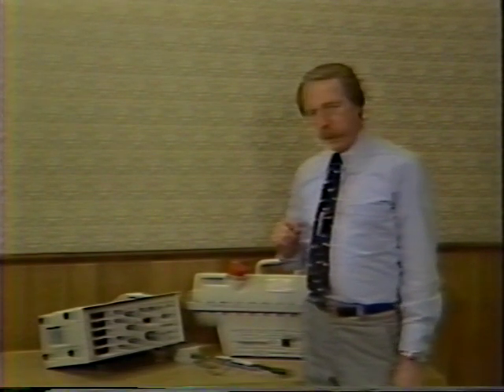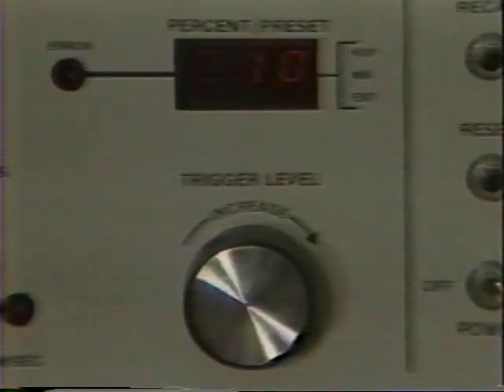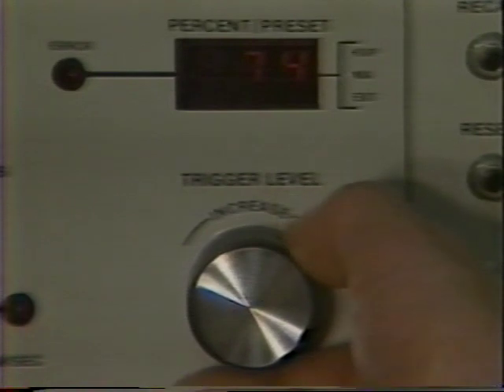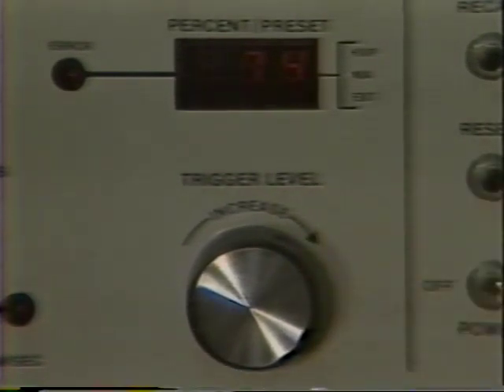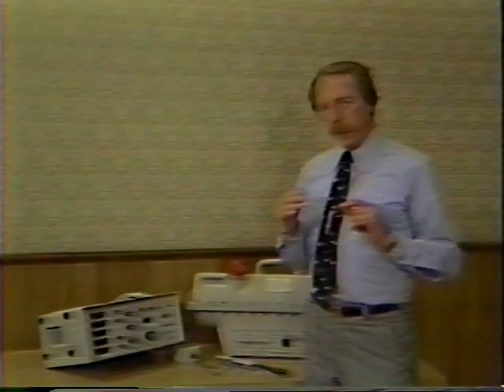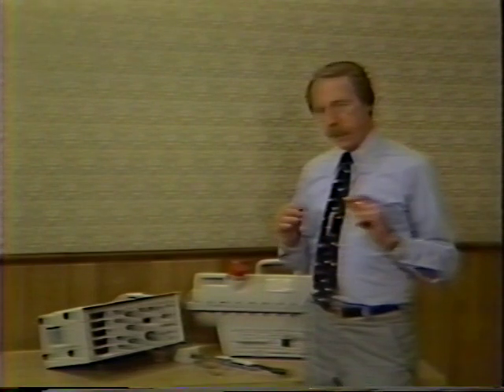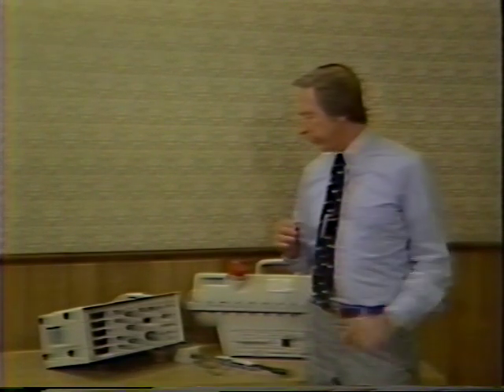It is our understanding that most American manufacturers, General Electric, Picker, Raytheon, Xonics, will trigger off the 75% level. What we would do is then dial in 75% into the trigger level control, take our shot, and assume we had 100 kV set into the generator. We would then trigger our digital clock at the 75 kV level.